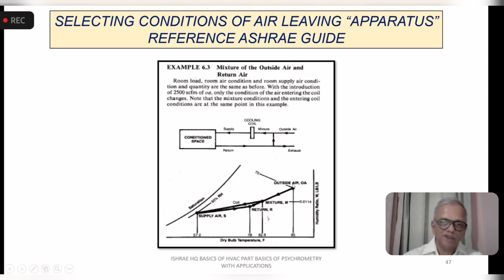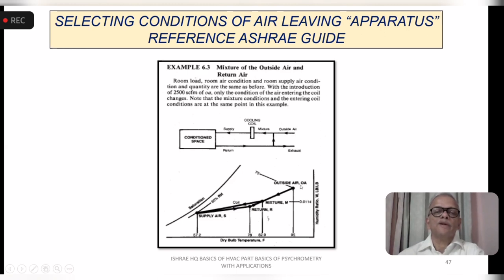The way it is, you will see the outside air here. You know the air quantity, the outside air CFM we are giving. For the return from the room, you will assume the room design itself as the return air. At times, if the return air passage is long, you have to add a certain sensible heat to it to get the correct value before it mixes. Then you calculate the mixture. You know the condition of the mixture depending on the proportion of return and outdoor air. You pass it over the coil using the sensible heat factor, and then you supply to this room, which means you supply at this point and it is cool enough to pick up the room sensible heat and dry enough to pick up the latent heat. That's what I mentioned in the previous slide. So this is a typical air conditioning application where you use outdoor air and return air, and the mixture is passed over the coil.